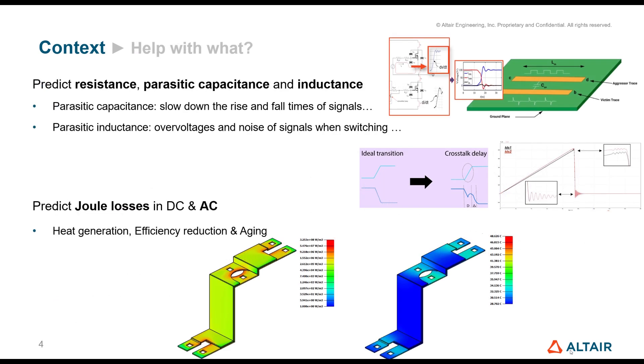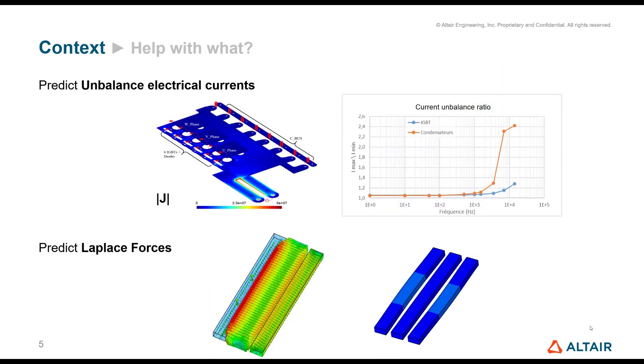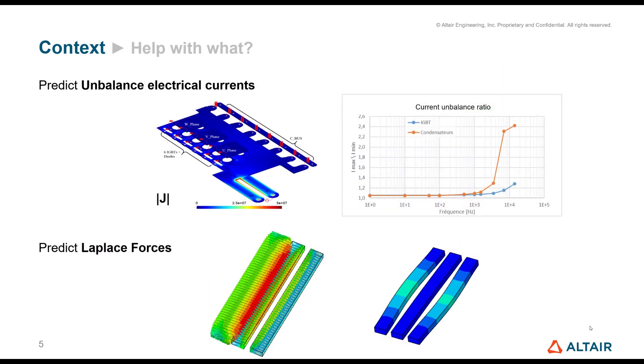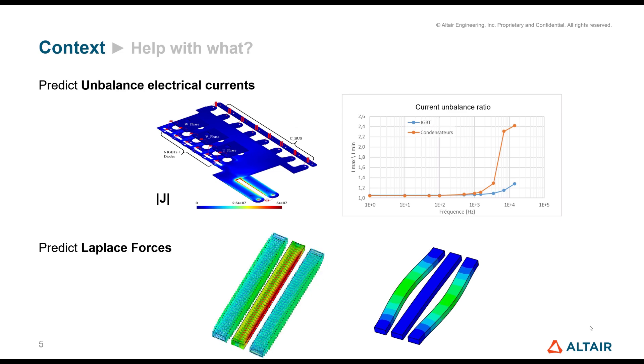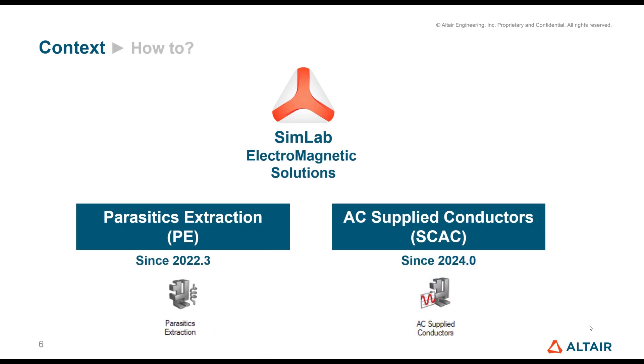What we can do with this solver is on one side predict and compute all these parasitic behaviors - get their impedance and extract them. The second part is to supply the device where we can predict all the joule losses, DC and AC losses, predict where the current is going inside the busbars, and predict all these forces. Knowing that, we can then couple these results to other multi-physics behavior. We have two applications: parasitic extraction, and AC supply conductor, which we're going to focus on today.